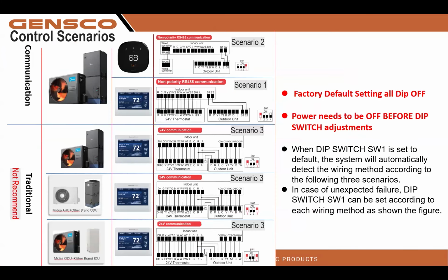Here is a look at our wiring, whether we're going 24-volt or fully communicating. And I will tell you that we recommend fully communicating all the time. It allows this system to function and run the way it is designed with the maximum amount of performance. Factory default, all the dip switches are off. The power to the indoor unit does need to be off when making dip switch adjustments. If you make dip switch adjustments while the system is powered up, you will need to power down that equipment and power it back up. Since we are talking about powering up and powering down equipment, when you install this equipment, indoor and outdoor, it is highly recommended that you power up the outdoor unit first and the indoor unit second.